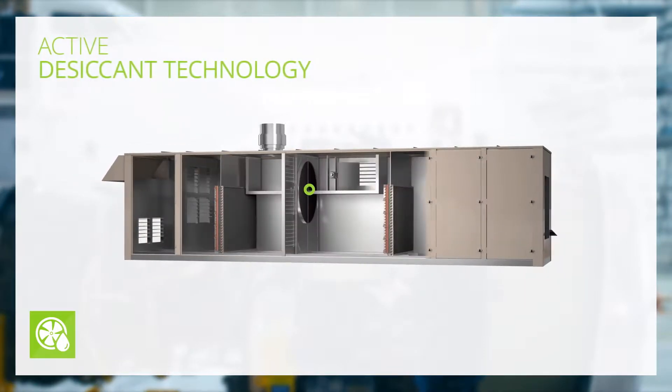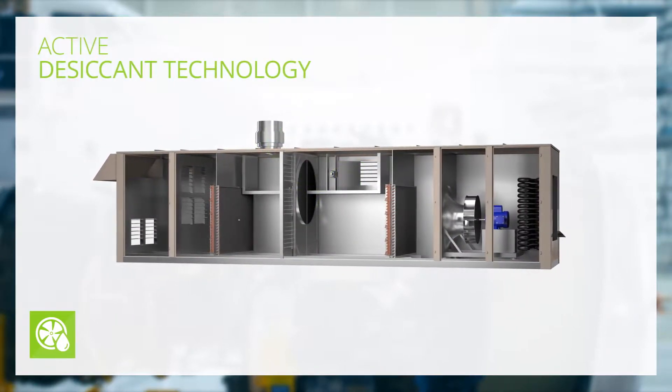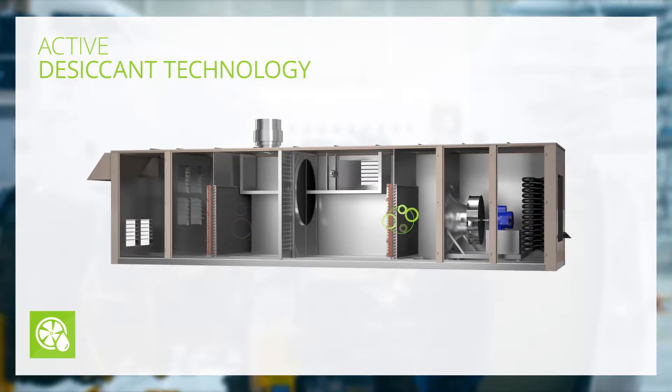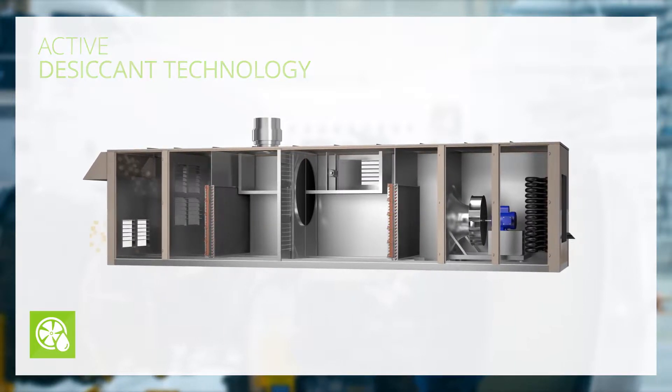Active desiccant technology incorporates a desiccant wheel and a heated drying cycle to remove moisture from the air. Traditional cooling coils are then used to reduce the temperature of the air to the desired levels.